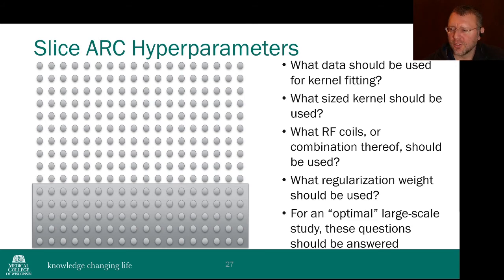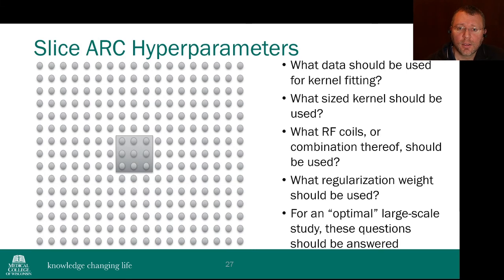And there's some folklore, and there's actually conflicting literature about how well your GRAPPA kernels do if you're fitting in the center of k-space to the edge of k-space. The spoiler here is that generally the edge of k-space, you get better results than if you fit in the middle where you have more signal, which seems a little counterintuitive. Conversely, if you're fitting those kernels, what is a good kernel to fit for that GRAPPA? Is it a nice symmetrical thing that's nice and small?